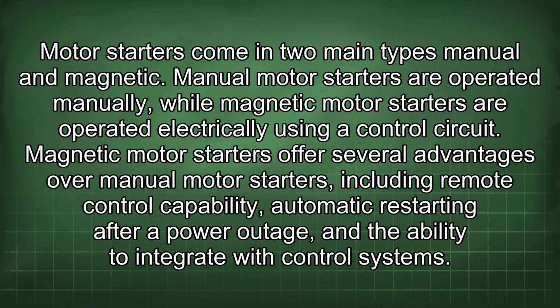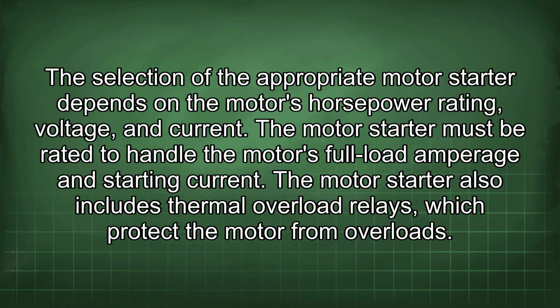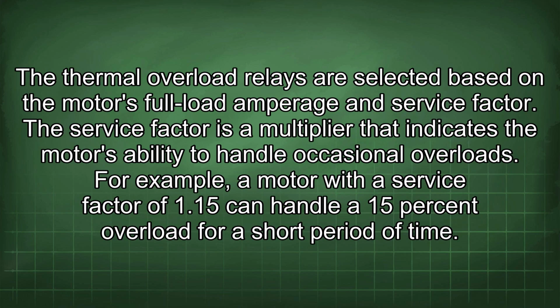Magnetic motor starters offer several advantages over manual motor starters, including remote control capability, automatic restarting after a power outage, and the ability to integrate with control systems. The selection of the appropriate motor starter depends on the motor's horsepower rating, voltage, and current. The motor starter must be rated to handle the motor's full load amperage and starting current. The motor starter also includes thermal overload relays, which protect the motor from overloads. The thermal overload relays are selected based on the motor's full load amperage and service factor.